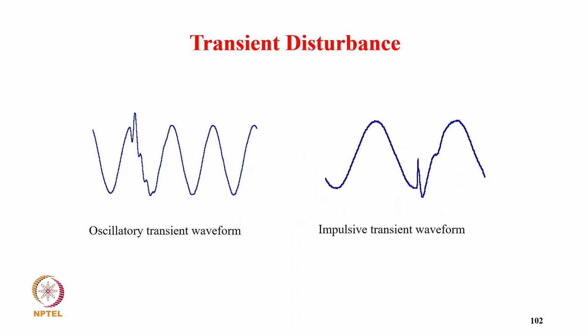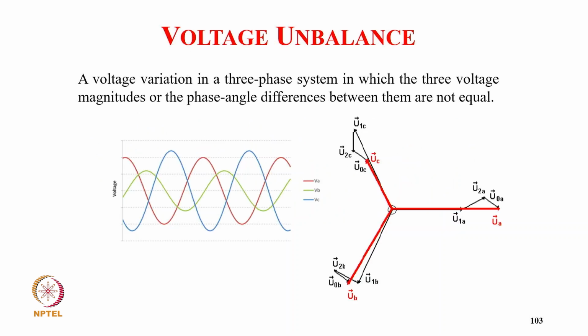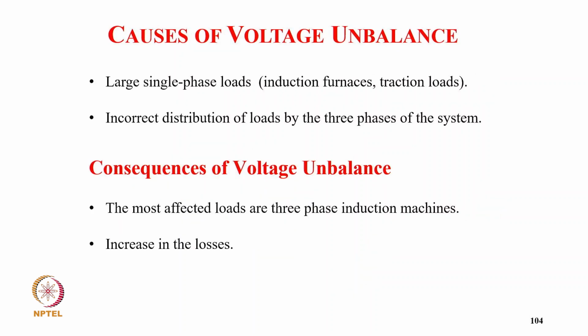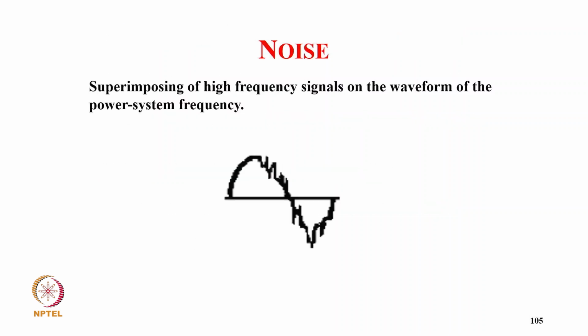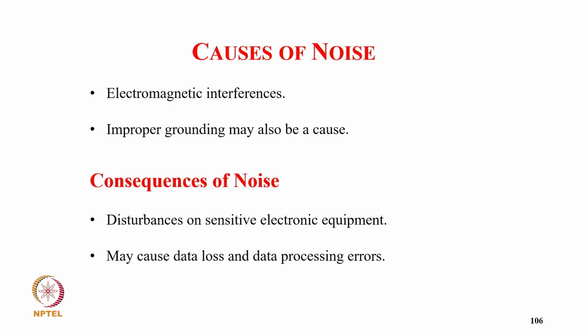Other disturbances are oscillatory transient and impulsive transient. Voltage unbalance is a voltage variation in the three-phase system in which the three voltage magnitudes or the angle differences between them are not equal. Causes of voltage unbalance: large single-phase loads, induction furnaces, traction loads, incorrect distribution of loads in the three-phase system. Consequences of voltage unbalance: the most affected loads are three-phase induction machines, and increase in losses. Noise is the superimposing of high frequency signals on the waveform of the power frequency.